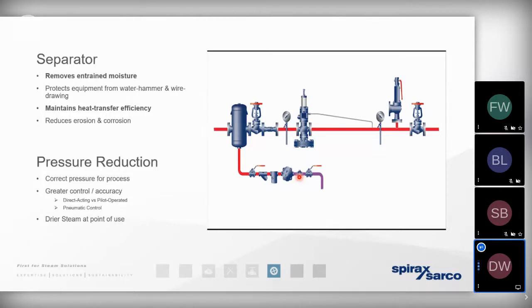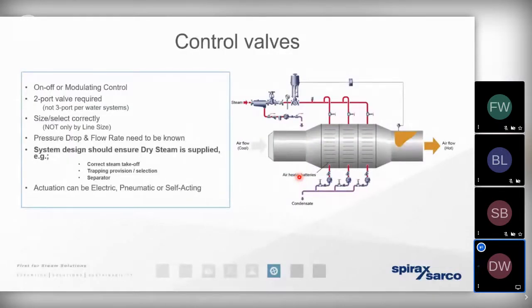So we know that one of the biggest problems that are faced by heat exchangers are that the control valves can be incorrectly sized. For example, if a control valve is oversized, it's going to spend a lot of its time operating very, very close to its seats. That's when erosion occurs. If we've missed off the conditioning ancillaries altogether, that's when erosion occurs, and that's when we're at risk of steam bypassing across the control valve onto the heat exchanger. So we either get an inefficiency from an energy perspective, maybe even the high limit valves and the relief valves pop in, or B, we get product spoilage.